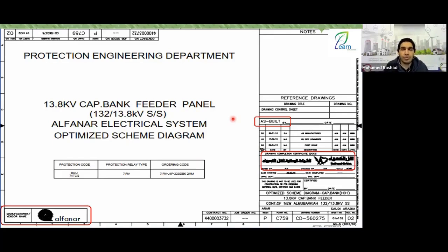So you start troubleshooting or doing something that doesn't match. This wire went from this place to that place, but it was modified with something added in between. Yet the drawing doesn't say that, or the situation doesn't reflect that. So you need to be aware of which version of the drawing you are holding. All right? Then we have a very important part here.